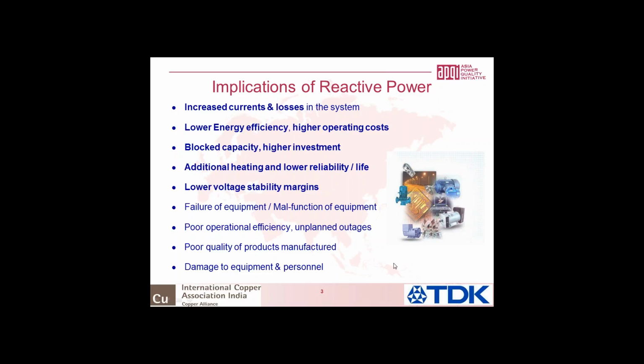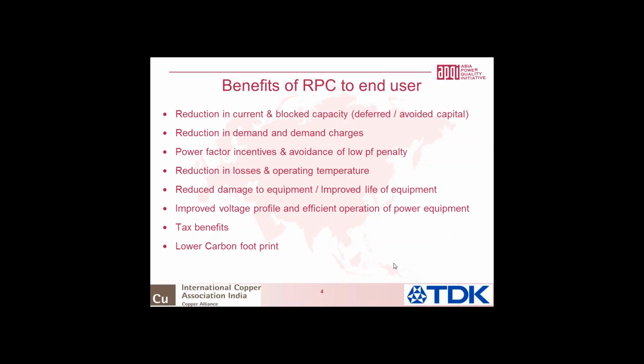Now the flip side of this story is, when you do reactive power management or reactive power compensation, the benefits are much easier to visualize. Yes, of course, there will be a reduction in current, which means there's a reduction in block capacity. You don't have to have a higher volt ampere rated cable, conductor, transformer or switchgear, which means I can go for a smaller transformer, which is deferred capital or avoided capital.